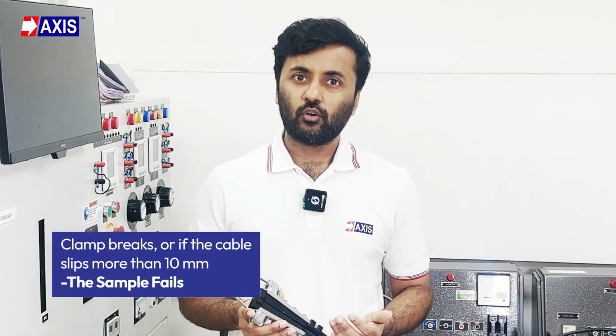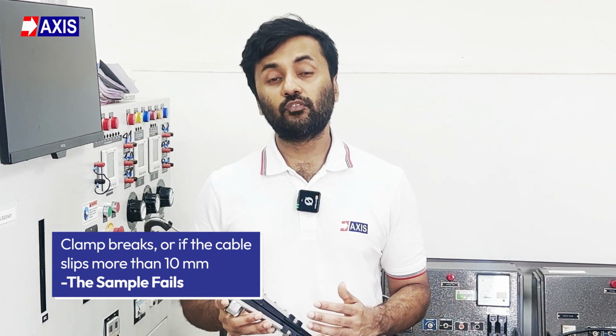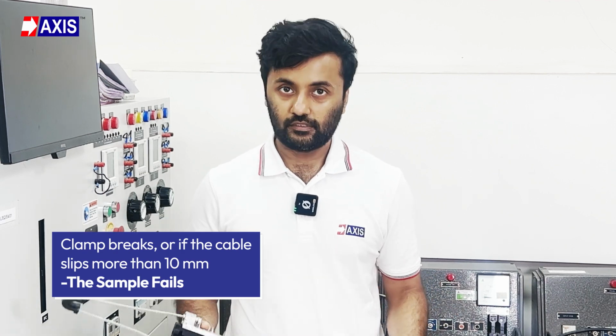After that, apply a second load of 6000 newtons. Hold this load for 60 seconds, then remove it. The speed of load application must be controlled between 5000 and 7500 newtons per minute, as per the standard. If the clamp breaks, or if the cable slips more than 10 mm from the marked point, the sample fails.